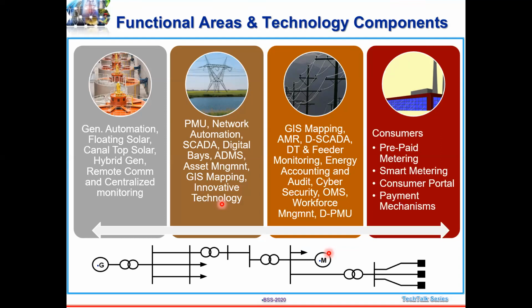In the transmission network, we have network automation already there. SCADA is already there. Digital bays is under execution for the smart grid - not 100% digital, but 70%, semi-digital you could say. Then we have automatic demand management system already in picture, where demand management is automatic. Based on load balancing from the LDC, a command will automatically be issued to the substations to shed or control the feeders so that demand is balanced with generation automatically.